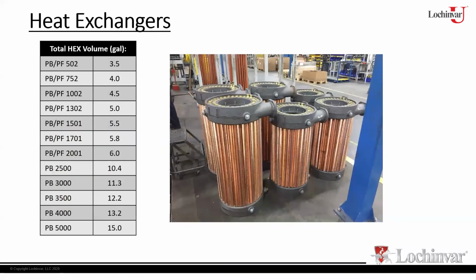Now, as far as the volumes of these heat exchangers, like all copper heat exchangers, these are low mass. So that means they've got very little water content in the heat exchanger itself. So as you can see, from 500,000 at 3.5 gallons, up to 5 million at 15 gallons, not a lot of water in these things. To give you an example, the 2 million has 6 gallons of water. If you compare that to a 2 million BTU Crest today, that heat exchanger has a little over 100 gallons of water in it. So again, a huge difference, same input, but a huge difference in water volume.